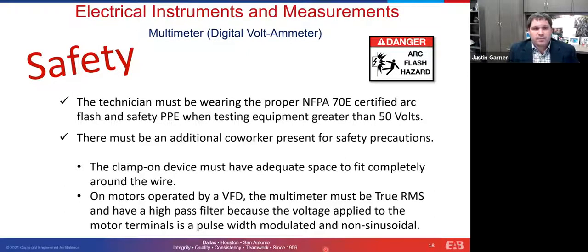And so to the motor, it looks like a sine wave, but to our meters, it looks like a very, very chopped up signal. What will end up happening is your meter, if it's not true RMS and doesn't have a high pass filter for this application, will read very differently than what the motor is actually seeing. And what we oftentimes see, if the filter is not engaged, is very high readings, especially if you're not close to 60 hertz and not close to full load amperage on the motor itself. Or off the drive, you'll get 520 volts on a 480 volt system. You just get some very off readings that would normally cause you to question the power system. But in this particular case, it would be an error on the part of the meter itself. So be aware of that and do some more research if this is new information to you.